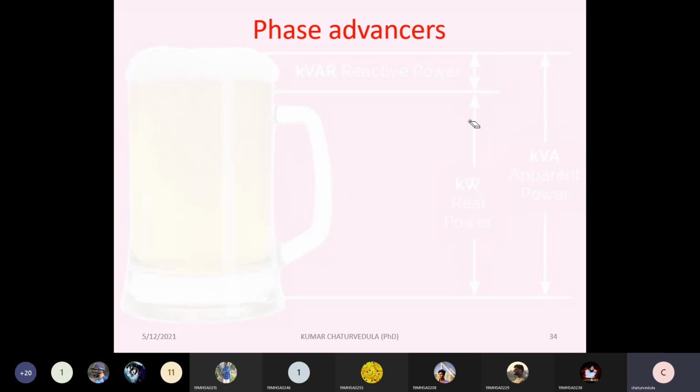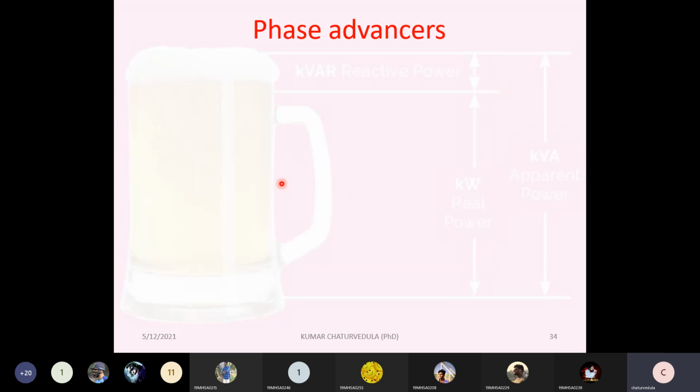Reactance X2r is S into X2, EMF E2r is S into E2. For every parameter in the running condition, there is a component multiplied with slip. That is why slip is such an essential component for an induction motor. Now we are going to utilize that key parameter of slip in this concept to improve the power factor.